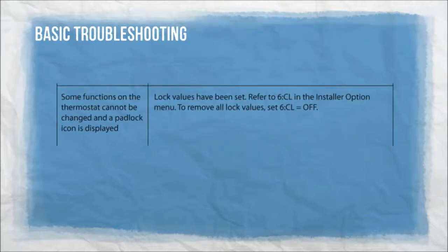Some functions on the thermostat cannot be changed and a padlock icon is displayed — lock values have been set. Refer to 6:CL in the installer option menu. To remove all lock values, set 6LC to off.